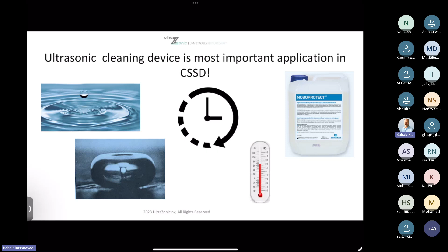As I told you, chemistry is very important. You have to respect some time, you have to respect some temperature, and you have to use a very good and decent disinfectant or detergent, which really helps to create this cavitation bubble, what you see on the left side under. This is really a picture of a cavitation bubble. Next, please.